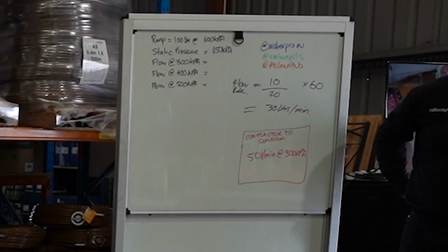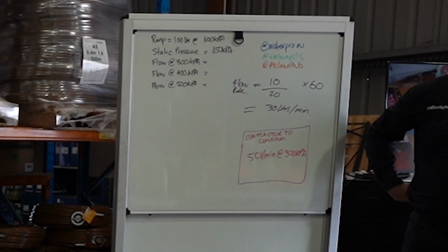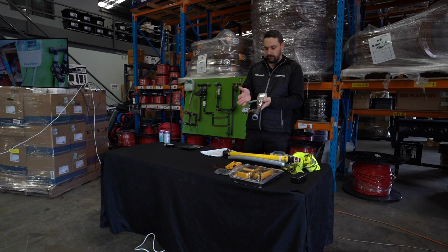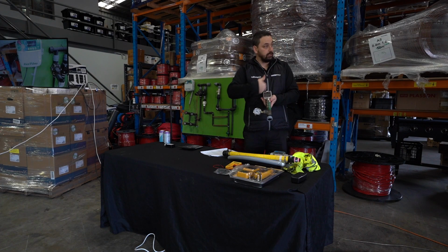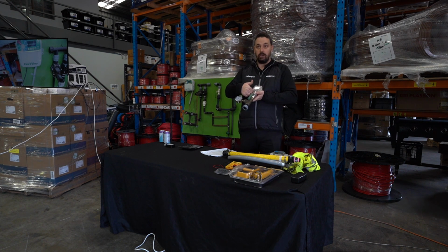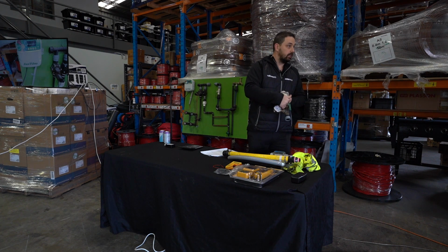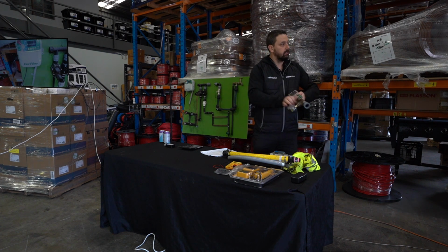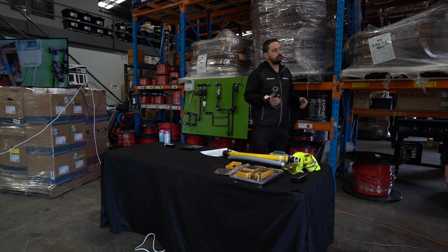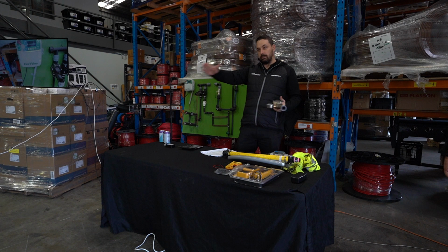So what we normally do, as Clint was showing with the pressure test kit, is on the tap we've had that open flow, and we would say, okay, on this one here, open flow might give us 100 litres a minute. So that will be a flow rate here at 0 kPa. That's our maximum that the system can deliver.